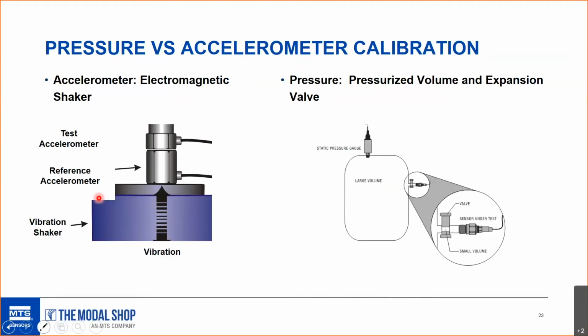On the other side, on the pressure calibration, we're doing a different technique. It's called a volume expansion. We call it a step rise. In this, we have a large pressure tank, which we call the large volume over here. Attached to it, we have a static pressure gauge, which we've calibrated very precisely. It's a large volume, like 5 gallons in this unit we'll see later.